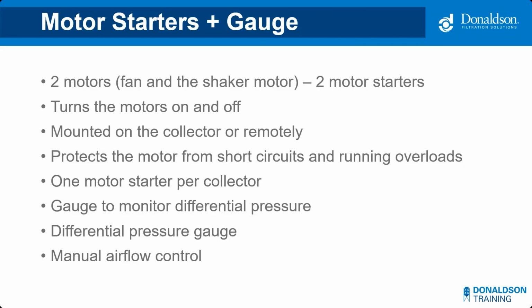Automatic shaker style collectors, that is the ones that use a motor to shake the filters, will typically need 2 motor starters per collector instead of just 1 like we previously discussed. Since shaker style collectors have a motor for the fan and a motor for the shakers, that's the biggest difference between everything we've discussed so far. Other than that, the list is exactly the same as the mist collector, including the differential pressure gauges that allow you to tell the status of your filters.